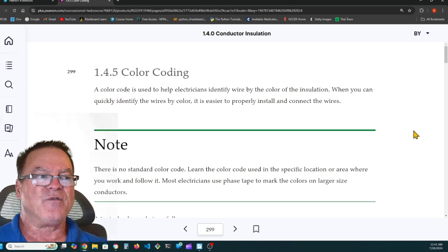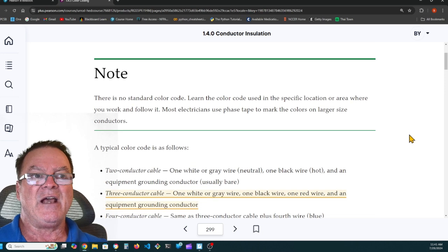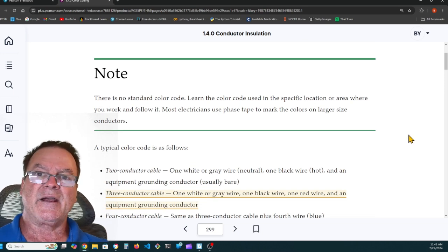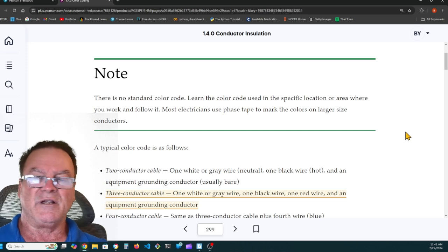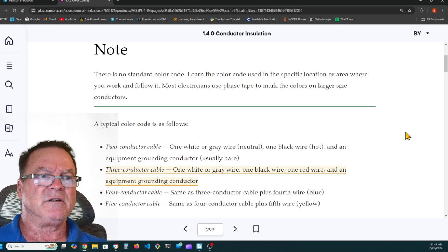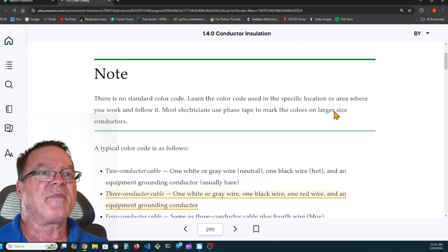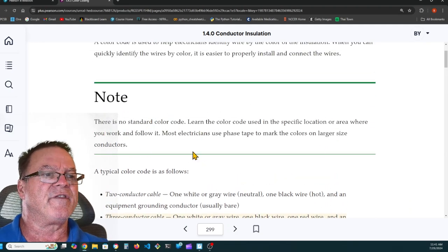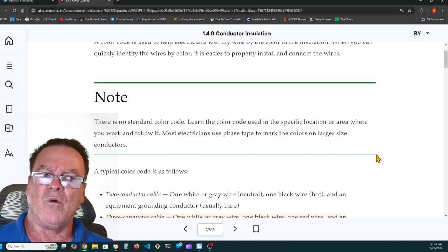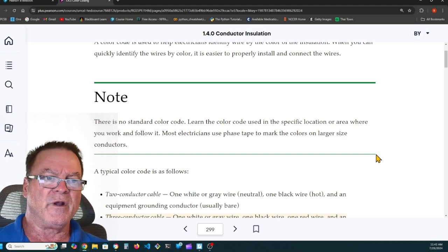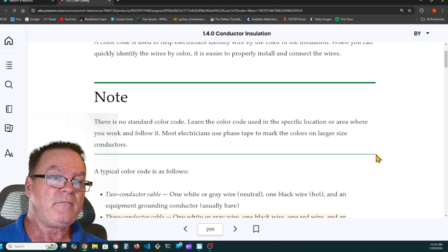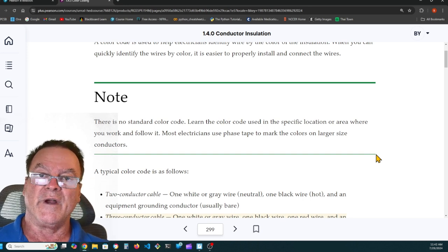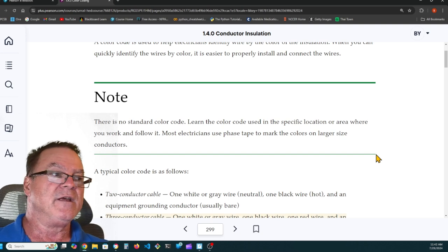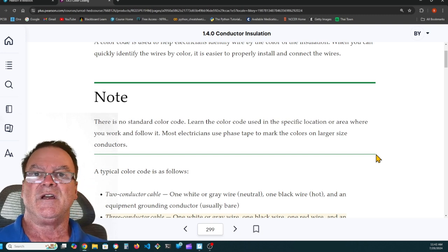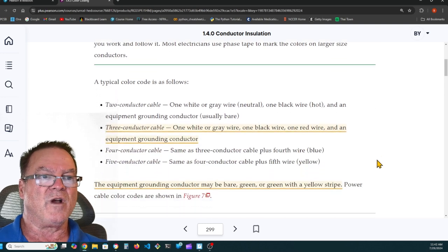We cannot use those for ungrounded conductors. We can use any other colors. So we can use black, red, blue, brown, orange, yellow, purple, magenta. But there's a rule of thumb in the electrical trade that for low voltage, and I mean 120, 240 volt, we use black, red, blue. If it's a higher voltage of 277, 480, we use brown, orange, yellow. So you'll get used to those different designations of color coding.